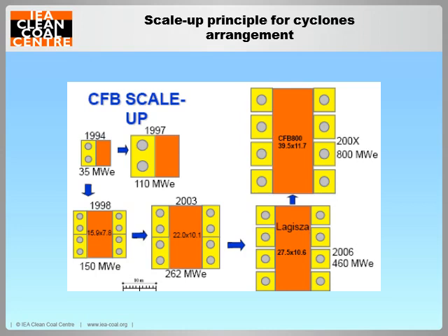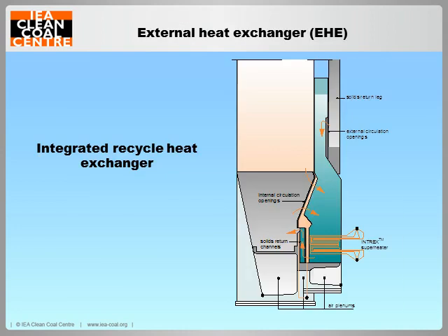For scaling up, cyclones of a proven size and design, with the optimal arrangement of the cyclones, are used. This figure just shows the principle of the cyclone arrangement for scale up. For large CFBC boilers with reheat, it may not be possible to perform all the required heat duty in the furnace and the backpass, so external heat exchangers are needed.